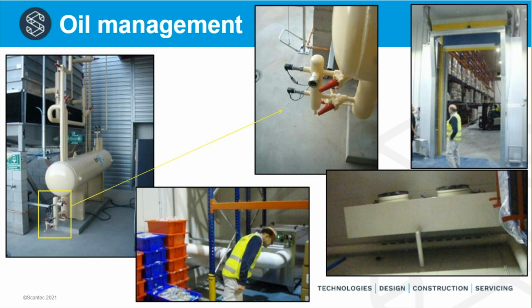The tank, or the receiver, that you see towards the left in the picture is a so-called high-pressure liquid-based oil separation system. Inside that receiver, there is a quiet area where the oil can settle down to the bottom of the tank. And once the refrigerant has been cleaned of oil, it spills over into another tank that is at the very end, the end pointing away from the picture. And from there, liquid is fed to the refrigeration system.